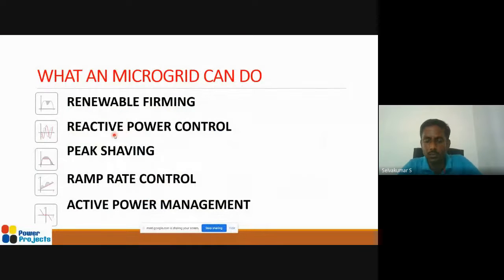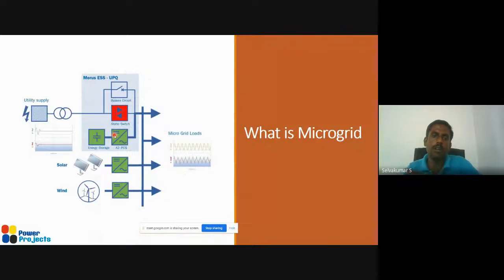So what else can it do? It can support reactive power control, and I guess the faculties from power electronics could find this good material for research on the PCS and its behavior. It serves quite a lot of purposes - it can act as a STATCOM, supporting reactive power, power factor, and voltage control. It can also support real power charge/discharge - real and reactive power in both directions are independently controllable.